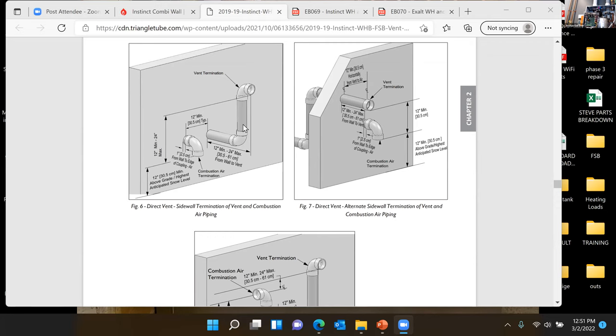I kind of like using the analogy of a car. We have our intake for the fresh air for combustion coming in the front, and we have our exhaust in the back. So these are just minimals, but the farther we can keep away the exhaust and the intake is better. Prevents that cross-contamination down the road. Not going to be an issue up front, but 3 years, 4 years down the road, we can definitely see the cause of it. So if you look on here, our air intake is just coming out and 90ing down. So on this intake, 100% every install, we got to try to 90 that down.